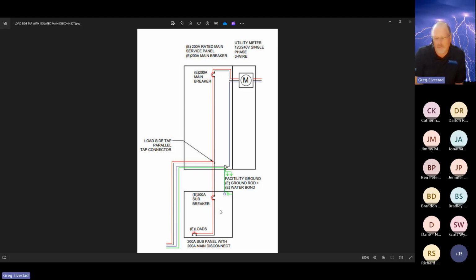And the brilliant code-making rule-making teams figured out, well, there's two different options here. A, we've got to worry about this chunk of wire being able to handle 240 amps. Not practical. The reason I say that is because most homes, probably 99.7% of the homes in the country, had subpanel conductors sized to this service rating, 200 amps. Well, guess what they used? They didn't use wire rated for 200 amps. They used 1/aught aluminum or 4/aught aluminum or 2/aught copper. Neither of those is actually listed for 200 amps.